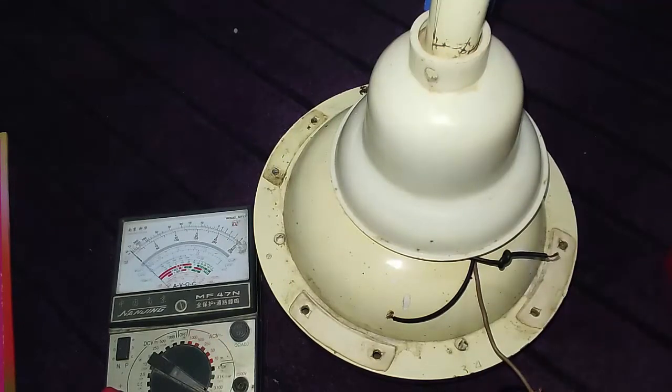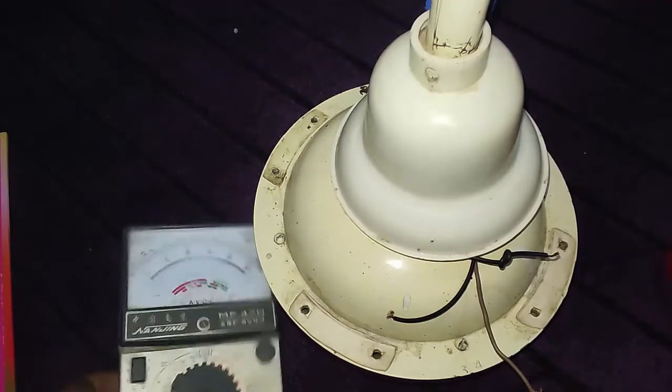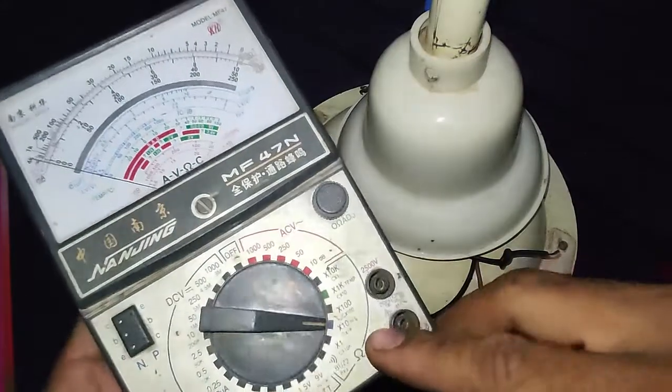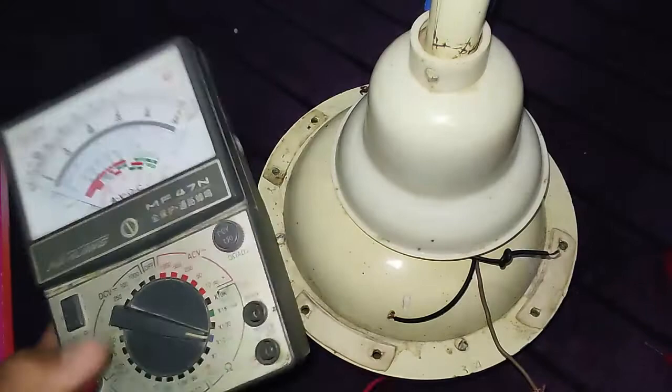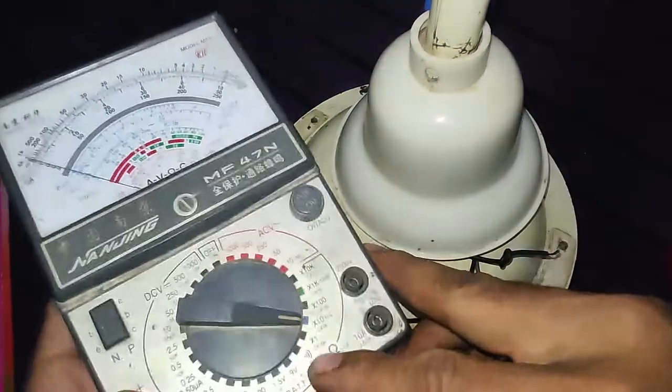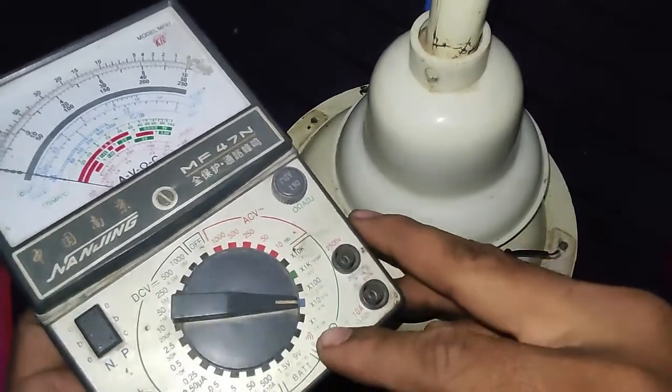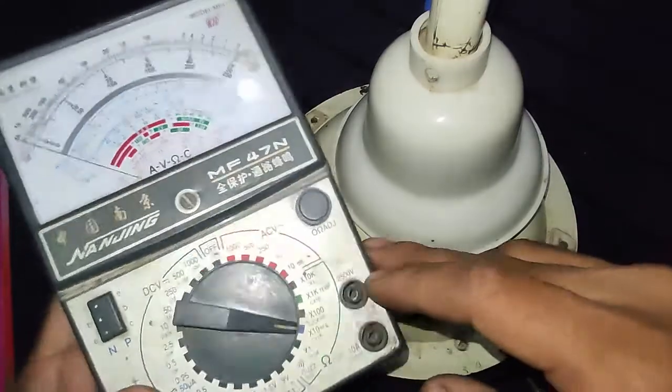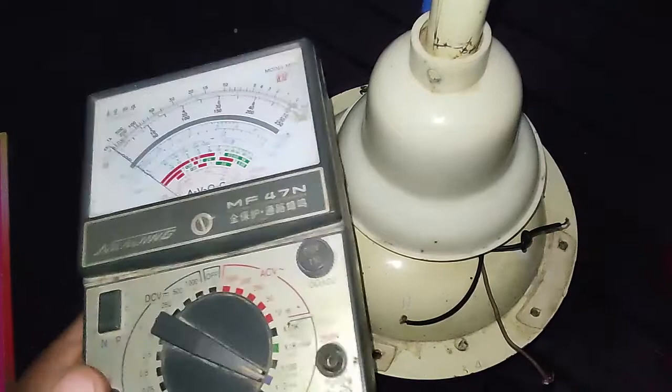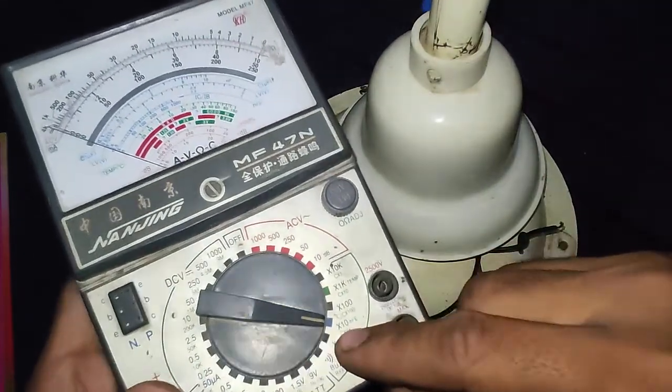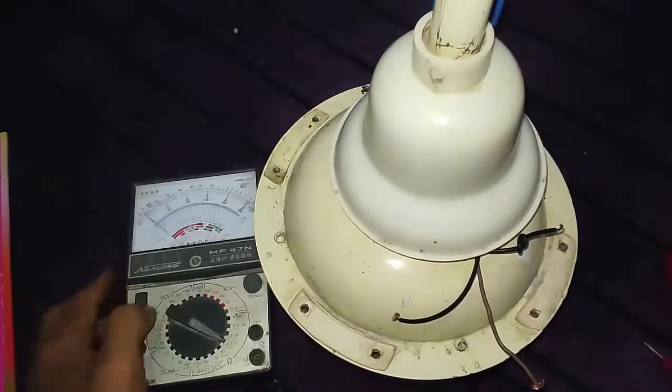First of all, I will set this multimeter on ohm testing. I have different connections, so I will set this multimeter on ohm testing and I have different testing modes: x1, x10, x100. For this type of testing, because the winding resistance will be high, I need to test with x10, so I will set on x10 mode.